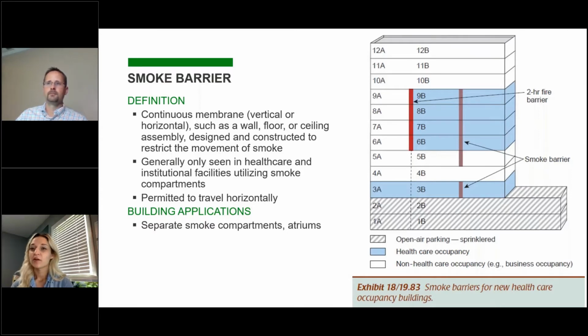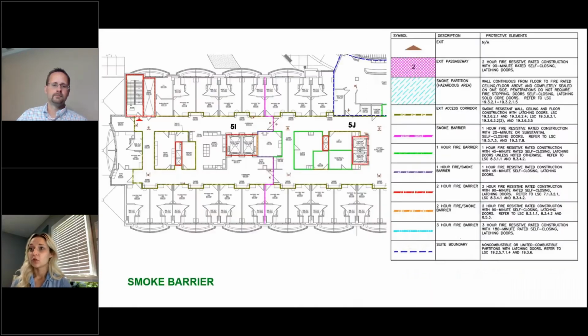Technically, a smoke barrier can be a wall or a floor or a ceiling, and the key term is that it's constructed to restrict the movement of smoke. We typically see these in occupancies where occupants cannot egress readily on their own. So think healthcare occupancies or prisons, where we are going to employ strategies to egress people horizontally throughout the building, so moving them from compartment to compartment. We see these to separate smoke compartments in healthcare occupancy, and also there's some requirements regarding atriums being separated with smoke barriers as well. So this is a great example of a plan.